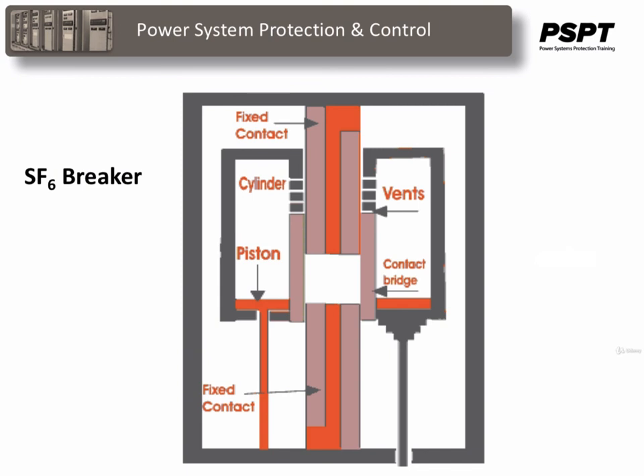Here is a diagram of the breaker, and it's filled with SF6 gas at rated pressure. There are two fixed contacts fitted with a specific contact gap. A sliding cylinder bridges these fixed contacts. The cylinder can actually slide upward and downward along the contacts. There is one stationary piston inside the cylinder, which is fixed with another stationary part of the SF6 breaker in such a way that it cannot change its position during the movement of the cylinder. As the piston is fixed, the cylinder is movable or sliding. The internal volume of the cylinder changes when the cylinder slides.